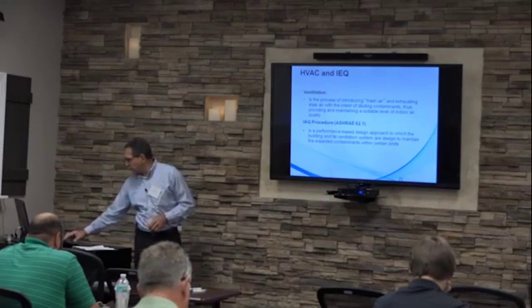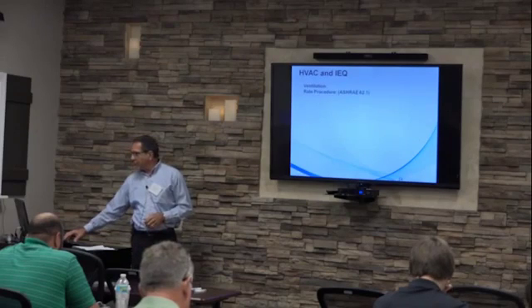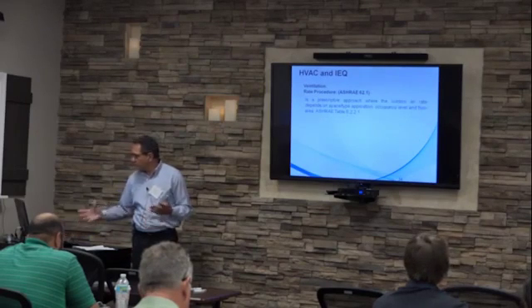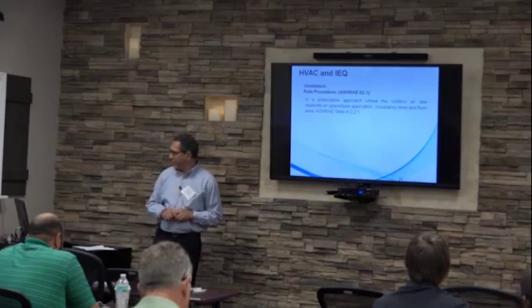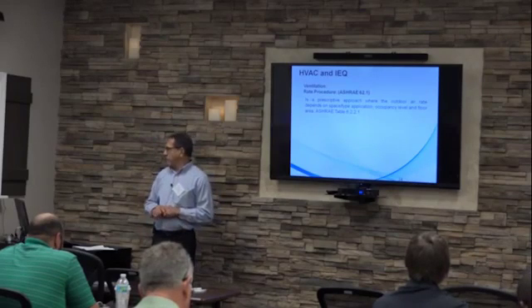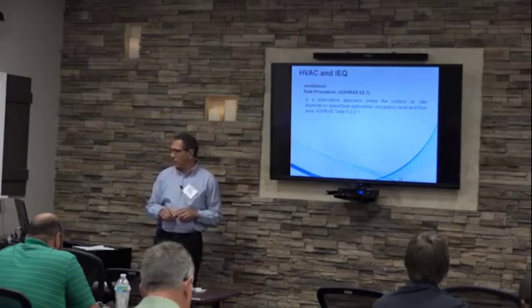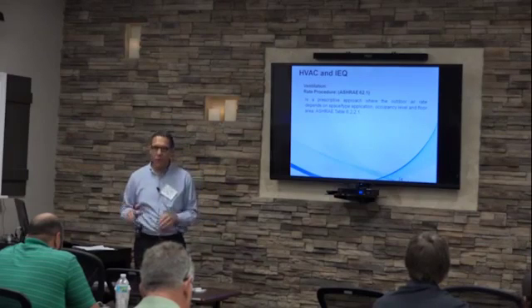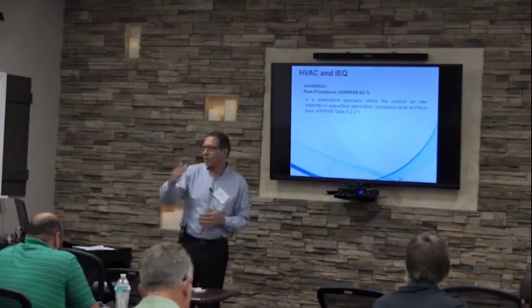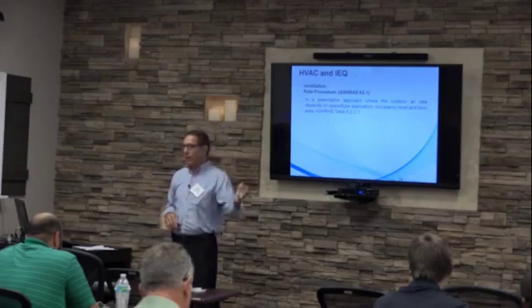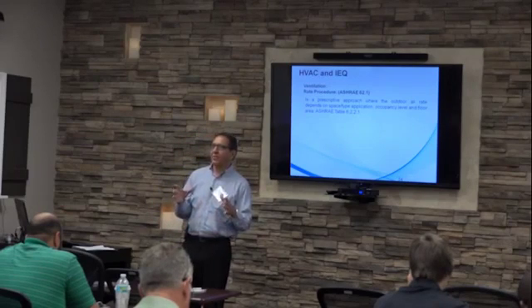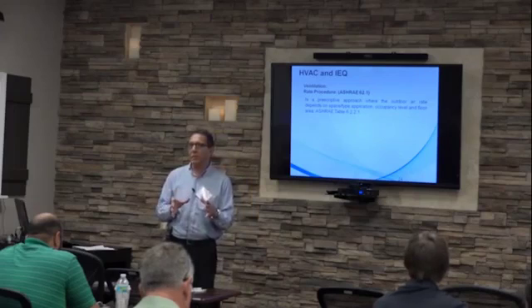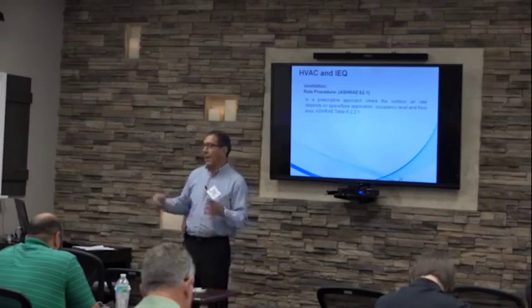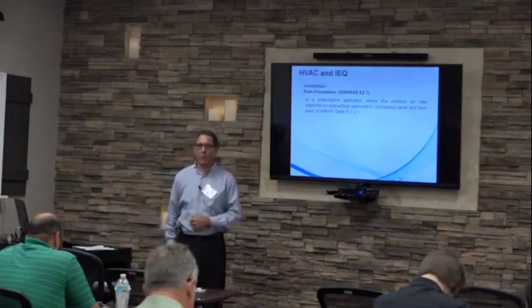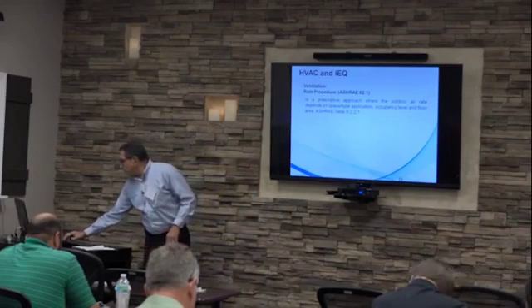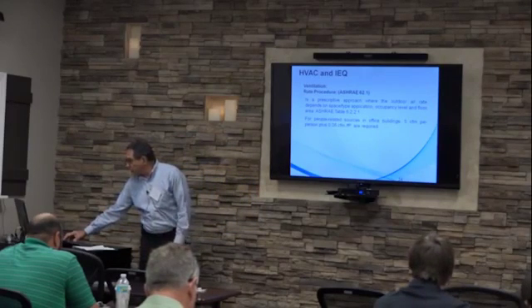ASHRAE 62.1 says you can comply with ventilation rates using the IAQ procedure, or you can comply using the rate procedure, which is a prescriptive approach to the outdoor air rates. And it depends on the application and occupancy of the floor area that you're dealing with. For instance, if you have 10,000 square feet and you have 50 occupants, then you have to have a certain amount of fresh air brought into the building based on the number of occupants and on the size of the building. Okay?